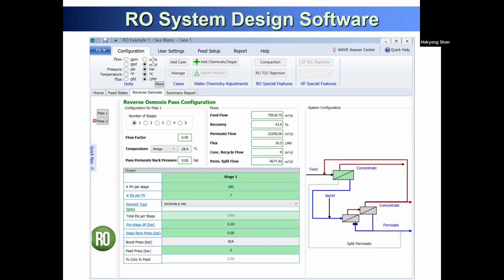In this case, you design for a 5-year membrane lifetime. If you always put in a new membrane, that means your ideal flow condition. However, the real condition is that the performance level is always decreasing. So we normally put in an extra 10%, so 0.9. Even though your design is 100 cubic meters per day coming in, we produce 90.